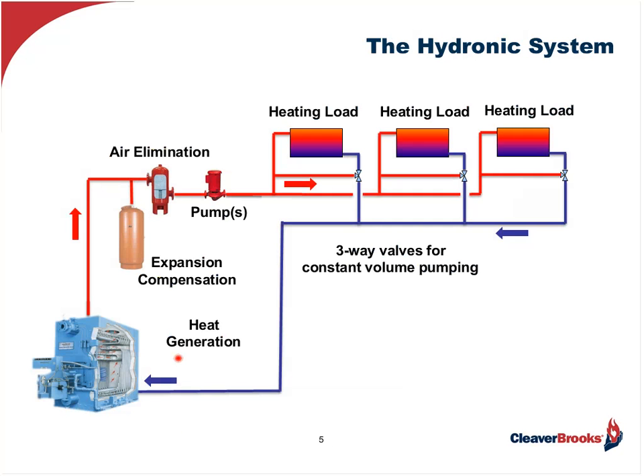And then you have expansion compensation. This is typically an expansion tank. It's important to remember that hydronic systems are generally closed systems, so as the water heats up, it expands. If we don't have some way of accommodating that expansion, the pressures will build to an unacceptable level and damage can occur to the system.